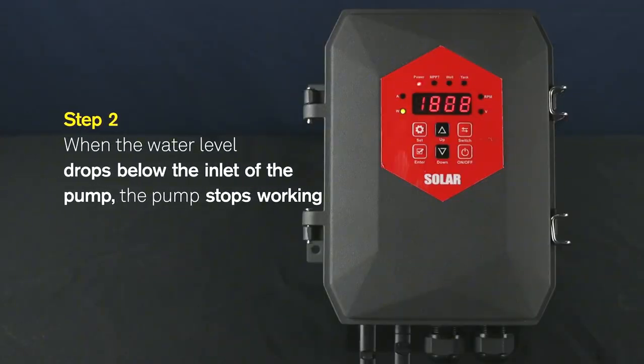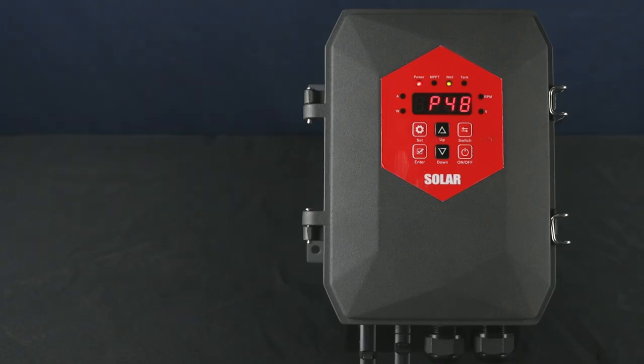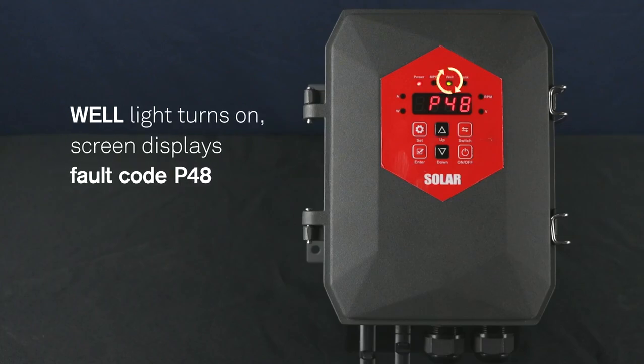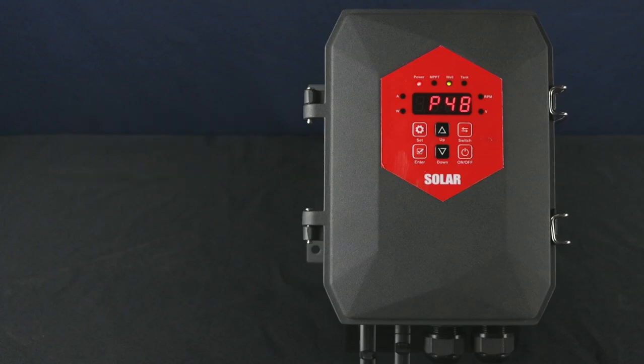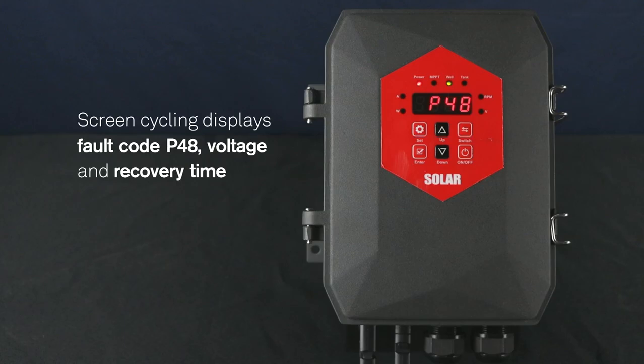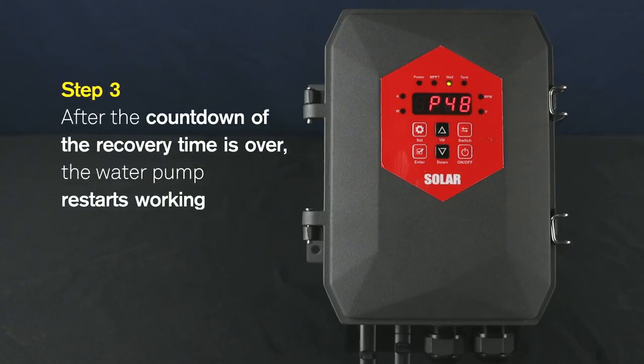Step 2. When the water level drops below the inlet of the pump, the pump stops working. Well light turns on, screen displays fault code P48. Screen cycling displays fault code P48, voltage and recovery time. Step 3. After the countdown of the recovery time is over, the water pump restarts working.